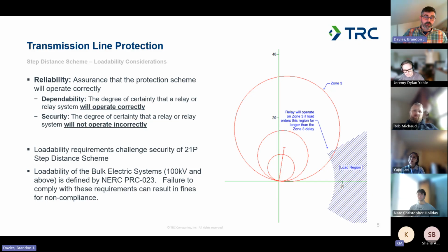Every transmission line, or really every current carrying piece of equipment in a substation, especially at the transmission level, has a continuous rating or multiple ratings that we can use to say this is how much power you can transmit through this device. And those are used in the operation of the system, so the system operators will know if they're pushing the limits of a specific piece of equipment.